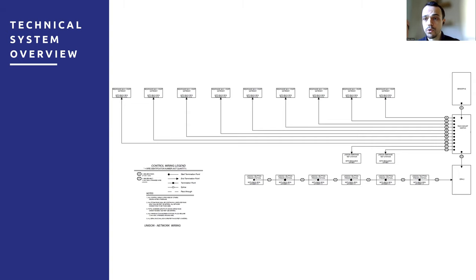Now, as mentioned before, Cat5e or Cat6 can only run about 300 feet. There will be instances where the run is actually longer than that. So there's a technology called a DMX splitter, which will essentially echo the signal that's sent and amplify it, allowing for longer runs. That's something that needs to be looked at based on the positioning of the processor and the different runs and distances inside of an auditorium.